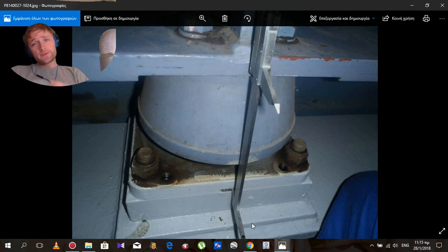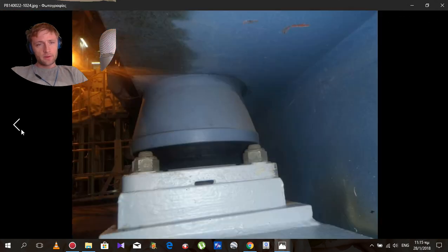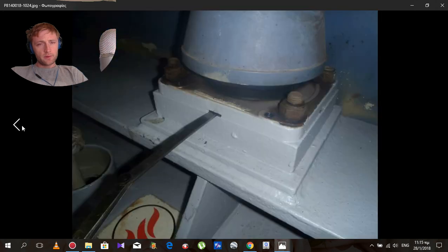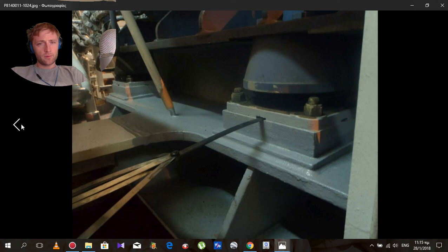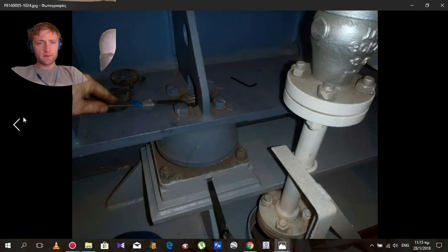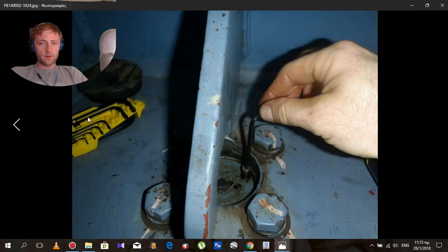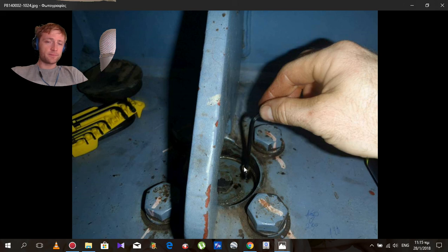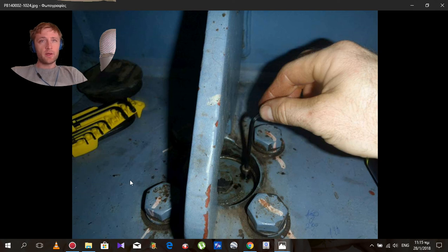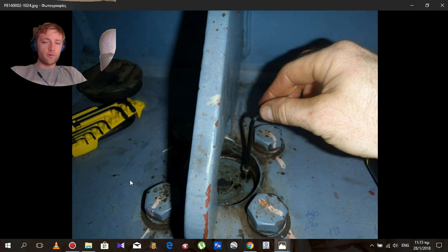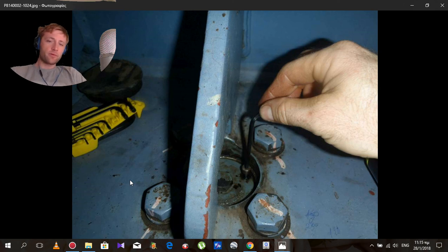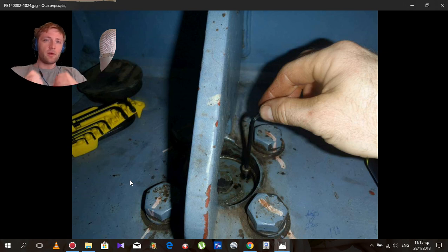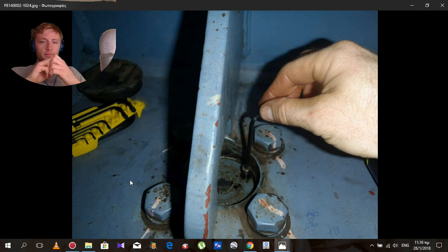What I have observed is the cleanliness, which is very important. But I have one condition I will show you which may be that resilient. Do not overtighten these allens. I have a condition where I cannot take out these bolts because they were so overtightened. Also, this resilient was moving. If you tighten that one and the resilient can hardly move or change position, it will be pressed, stressed more, and locked by the pressure.